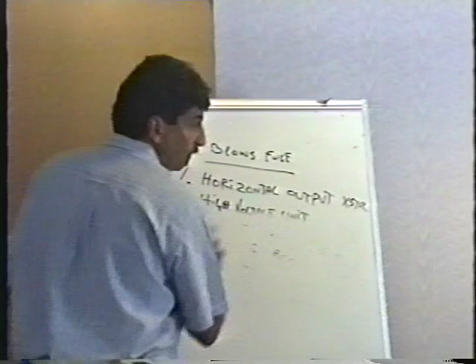If you look at the schematic drawing on page 57 of the high voltage unit, let's see what's inside it. You can see that the main part of the high voltage unit is a transformer. You'll notice that this transformer, instead of having a solid line for the core, has a dotted line. That means the transformer core material is not iron. The transformer in the high voltage unit is made of a material called ferrite. I'll pass this around so you can take a look at it. It's not iron, it's kind of a compressed ceramic-iron mix, basically. It's called ferrite. The core of the transformer in our switching regulator power supply is made of the same material.